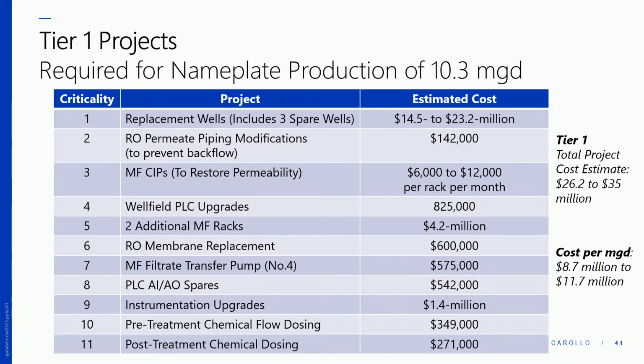The last two projects concern pretreatment chemical dosing. There have been instances in the past where chlorine dioxide feed during a plant shutdown and startup resulted in damage to RO membranes and loss of salt rejection. This project would address those shortcomings and automate the process so it's better protected and less reliant on a quick-acting operator to prevent the damage.